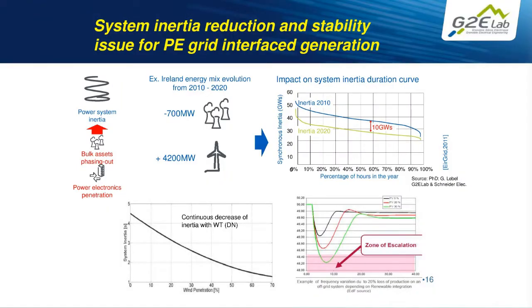Another concern on the overall grid is what's called the reduction in system inertia. In traditional systems we used to have large synchronous generating units, which are rotating machines, and rotating machines provide something interesting for the grid, particularly regarding stability: inertia.